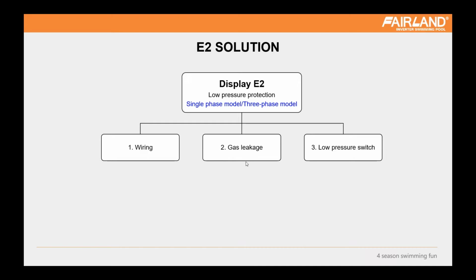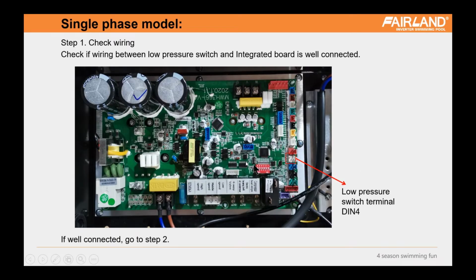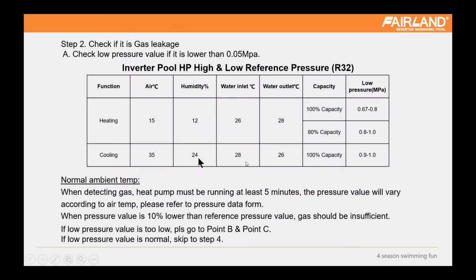E2, when E2 happens, simply we can consider it to be gas leakage, because normally this low pressure switch is always fine, very top quality. So when it happens, it is gas leakage. And if you don't have a refrigerant technician to check it on site, you can send an electrician to check the wire and check if the low pressure switch is fine. If it is fine and you show us the detection result, then we will understand it's a gas leakage. So you don't need to hire a refrigerant technician to check it. But of course, if you have your own refrigerant technician, it's best. You can check it directly, always.